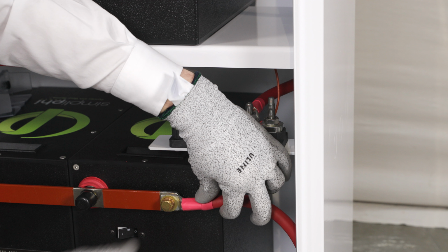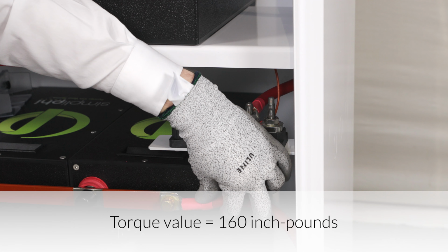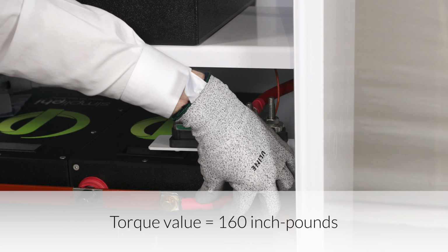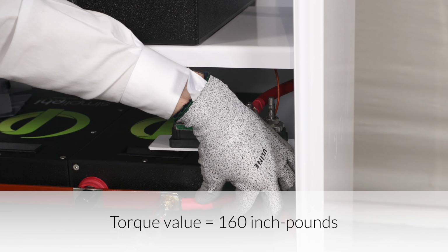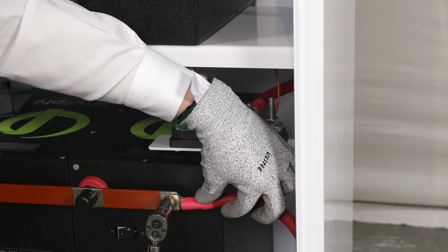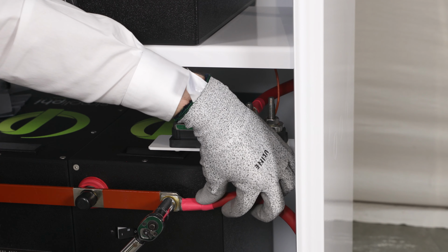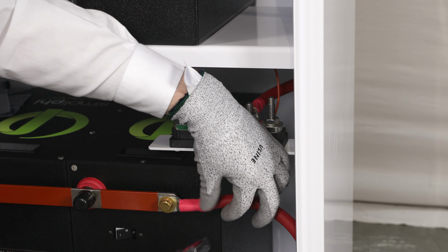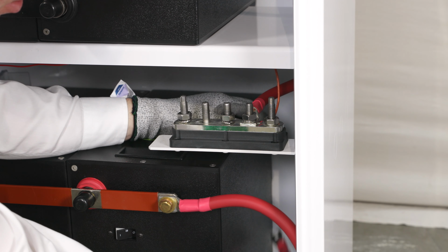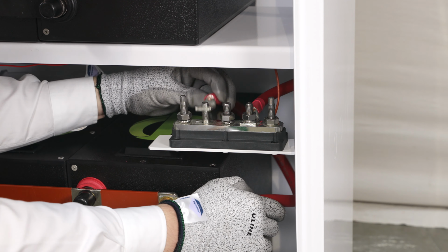Extending the cable directly towards the cabinet wall allows the cable to be routed more easily to the 5-point terminal block. Secure the cable lug to the bus bar by tightening the brass hex head cap screw to 160 inch-pounds of torque. While tightening, secure the lug with the other hand so that it doesn't twist or move. Route the cables back and up directly to the 5-point terminal block.